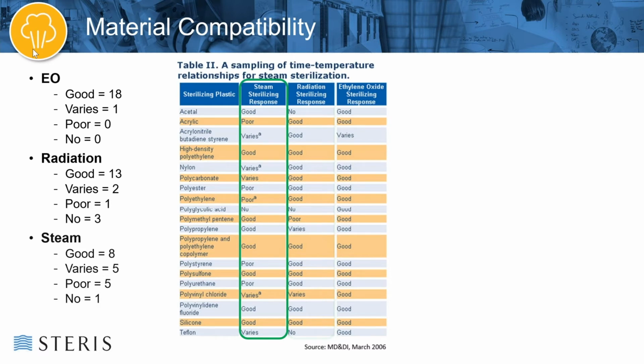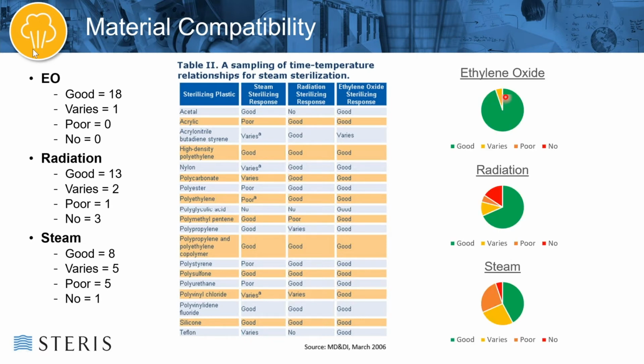And then for steam, you can see these just keep on getting less and less compatibility. So we have 8 of these items that are good, 5 vary, 5 are poor, and 1 of them is a no. And for those of you in the room who are more visual and like charts and graphs, like me, this is a visual representation. You can see up here for ethylene oxide, there's a lot of really good material compatibility. It drops down a little bit for radiation, and it's even less for steam.